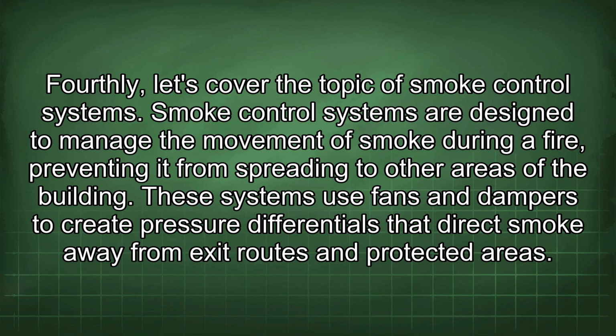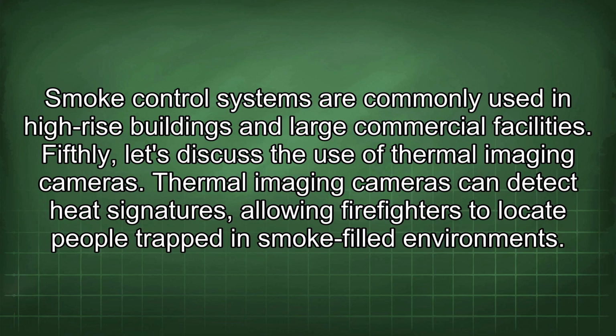Fourthly, let's cover the topic of smoke control systems. Smoke control systems are designed to manage the movement of smoke during a fire, preventing it from spreading to other areas of the building. These systems use fans and dampers to create pressure differentials that direct smoke away from exit routes and protected areas. Smoke control systems are commonly used in high-rise buildings and large commercial facilities.